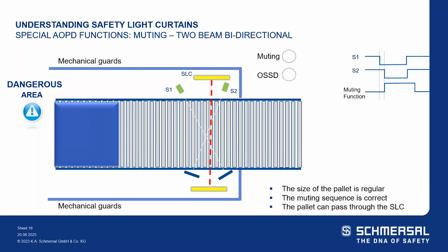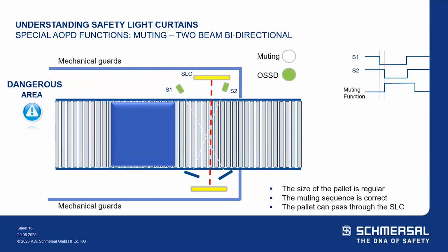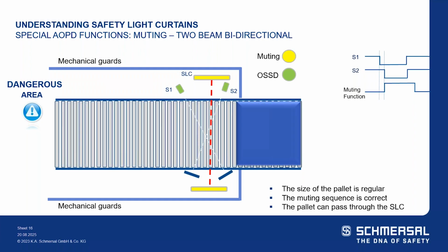And we're going to witness the fact that the size of the pallet is regular, the muting sequence is correct, and the pallet can pass through the light curtain.